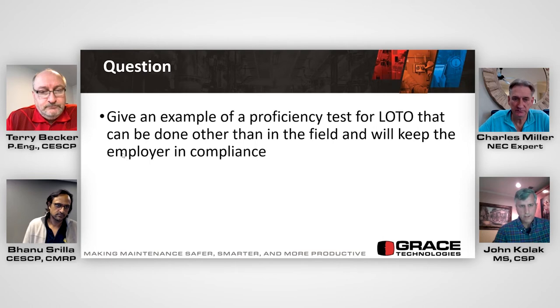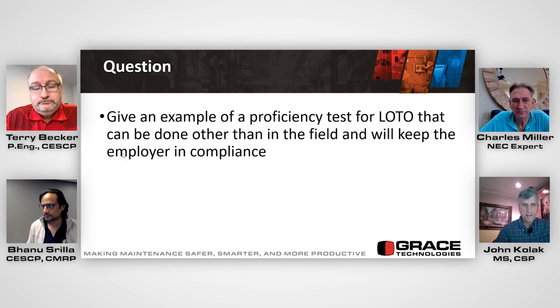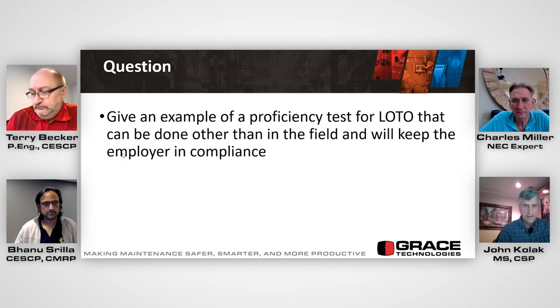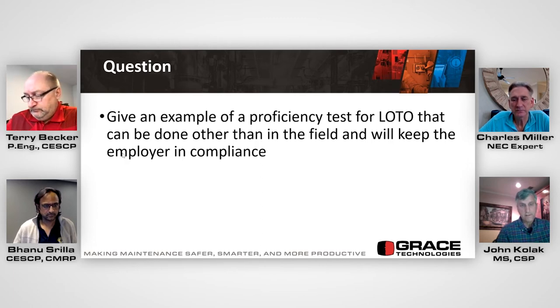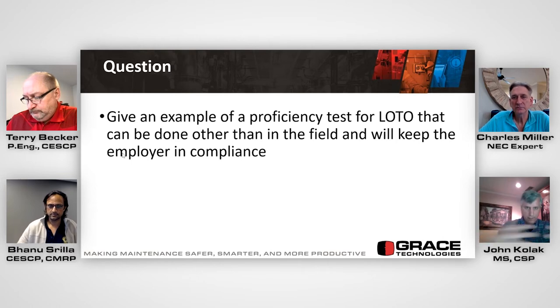Lockout tagout does not sit on its own. It is integrated into the overall switching and processes you're going to be using. So what I typically do for a field test is have the person do everything from the job briefing discussion through calculating the switching procedure, doing the switching, logging all that, getting to a zero energy state, and then returning it to service. If they can do that as the lead person under supervision, I consider that a demonstrated proficiency test for lockout, because lockout is inherent to the overall process. It is not a standalone process by itself. In fact, if you're in a fixed facility, you're required to have a standing set of switching procedures for the common switching done on site. Lockout is inherent to that. It's not like you do the switching and the lockout separately. They're integrated. I'll give Terry the floor for that.